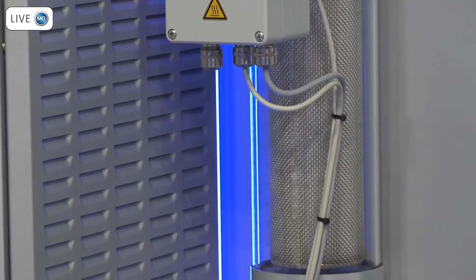Pretty good. So once you have installed, for example, this MESSKO MTraB, you never ever have to worry about checking the condition or replacing the silica gel. It's also good for the environment, so no more waste from that silica gel. This MTraB has a self-drying algorithm which dries out the silica gel and is completely maintenance-free.